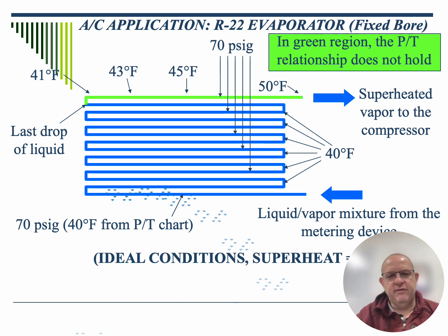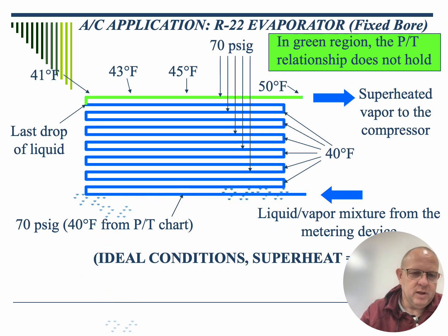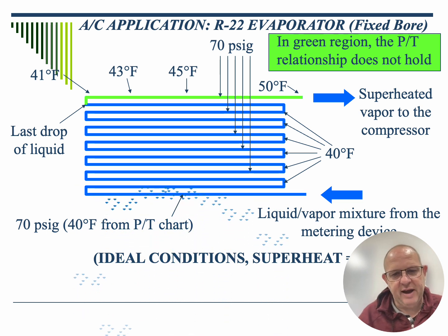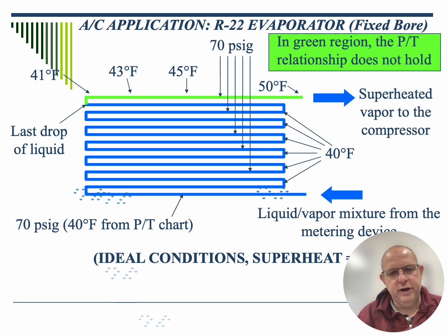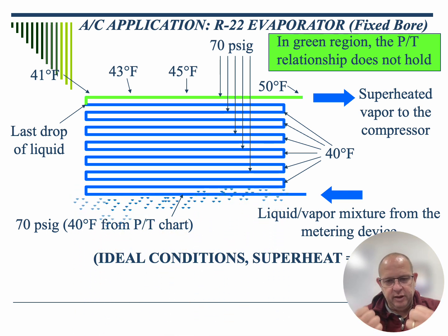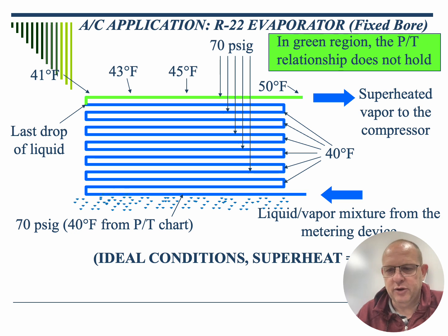As well, our evaporator should be sweating at this point. So we'll have condensation dripping off of the evaporator, because as that 75-degree air hits that 40-degree evaporator, it's going to draw the moisture out of the air, and then we're going to see a 17 to 20 degree temperature difference within that air.